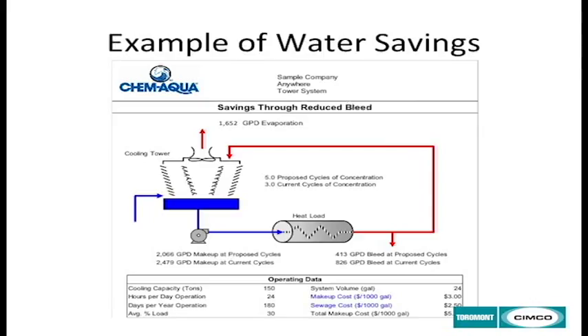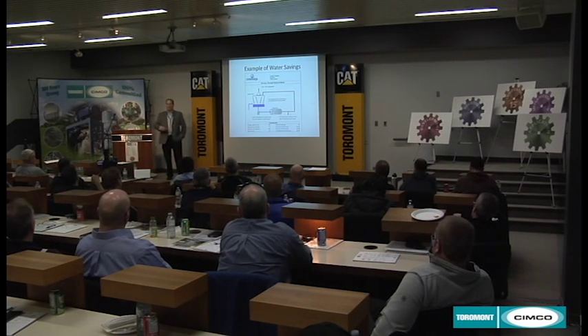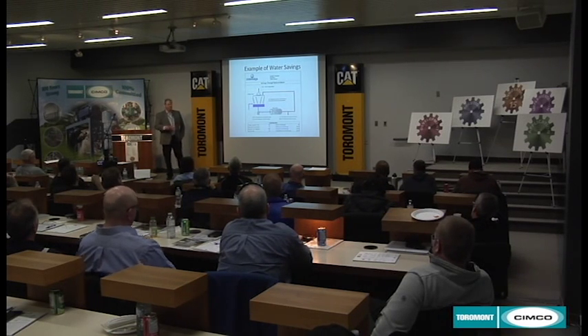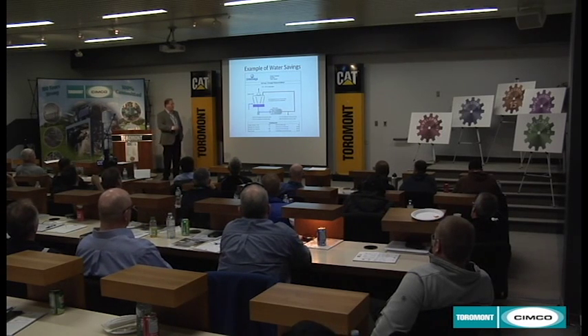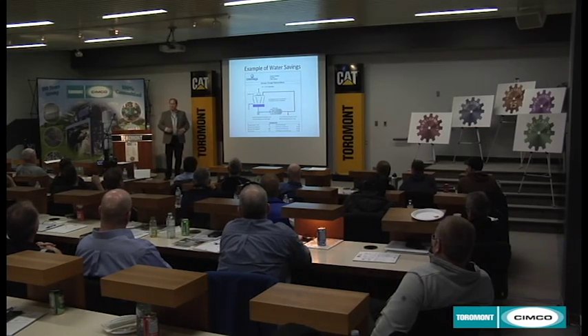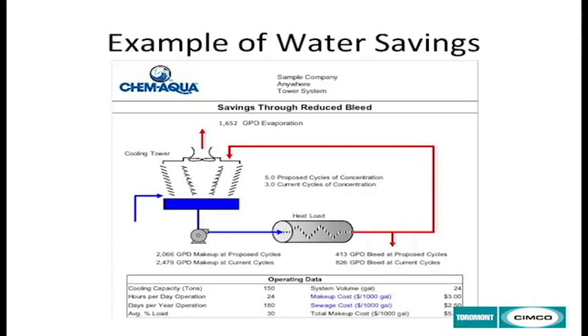But taking a look at a typical cooling tower, how it operates, or an evaporative condenser, you always have to have evaporation to cool the water. That water circulates in your cooling system, and as it circulates, it has to make up water for the water losses in evaporation. But to control the amount of solids that build up in that tower, we bleed part of that water to drain so that we control what's called the cycles of concentration. The more I drain out of that tower, the lower the cycles I have. The less I drain, the higher the cycles. Therefore, if I lower the amount of drainage or bleed that I cause, I could increase the cycles.